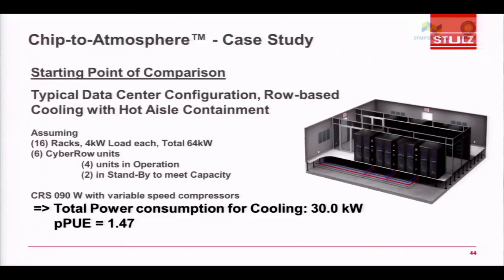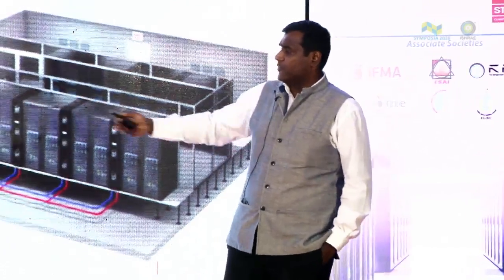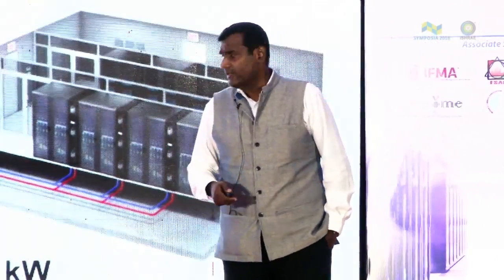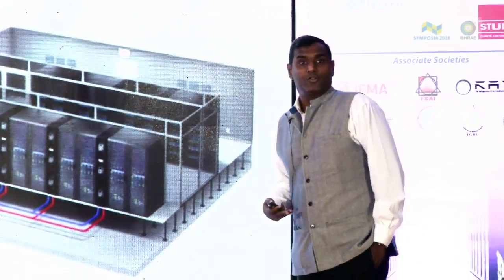A case for today where we are. If we have a 4 kilowatt rack and we have 16 racks, 64 kilowatt in total. Let us say we are cooling it with a traditional way. So with the traditional cooling systems, considering from a Stulz product line, a CRS90 product line with a variable compressor, that means you're using a good technology cooling system. A variable compressor is what today we know helps us to better the power consumption.